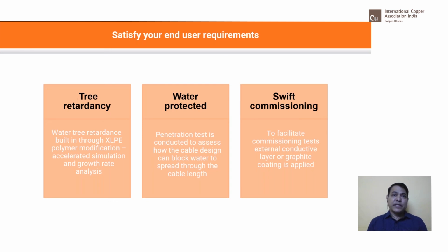I mean, there can be cracks because of high moisture or some water moisture. Insulation can become weak. The cracks can develop. That is what is called the formation of trees inside the insulation, which can weaken the insulation. That impacts the performance of the cable, and it can improve heat resistance as well if the compound is tested for the retardants, and enhancing processing. The retardant XLPE also gives good performance for the manufacturing. It is enhancing the performance of the CCV line.